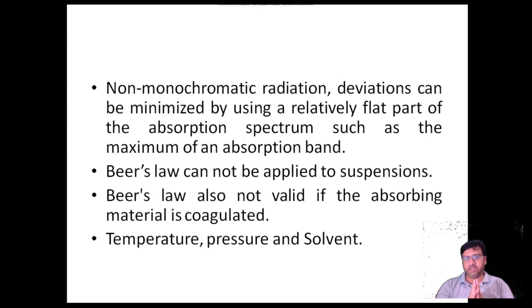Non-monochromatic radiation: these deviations can be minimized by using a relatively flat part of the absorption spectrum, such as the maximum of an absorption band. Beer's law cannot be applied to suspensions. It is also not valid if the absorbing material is coagulated. Other factors are temperature, pressure, and solvent.